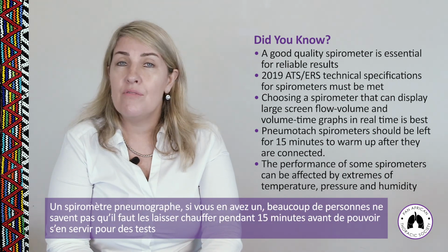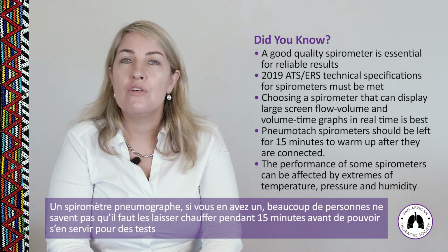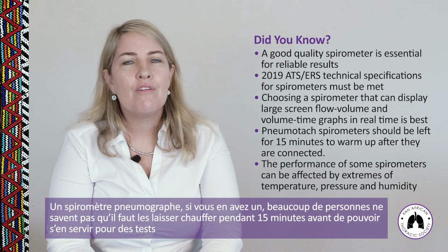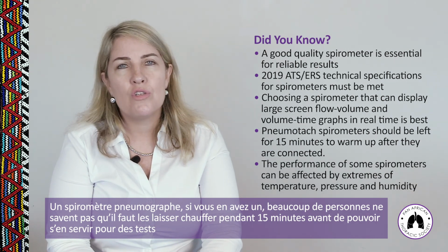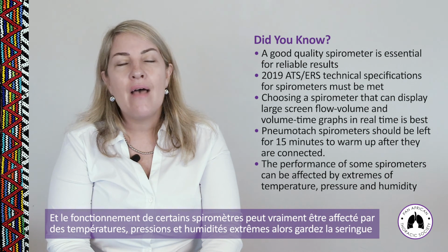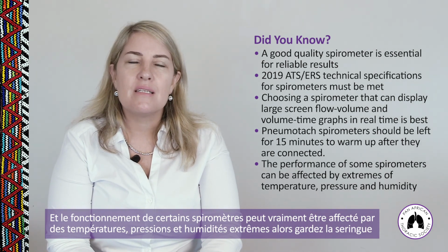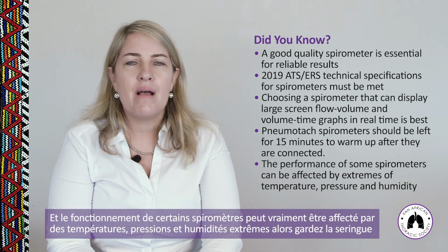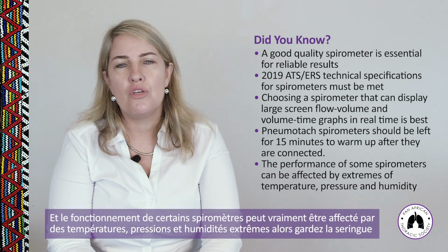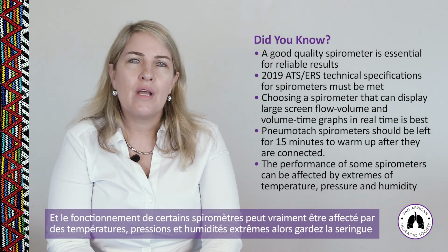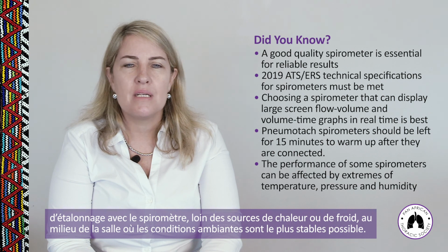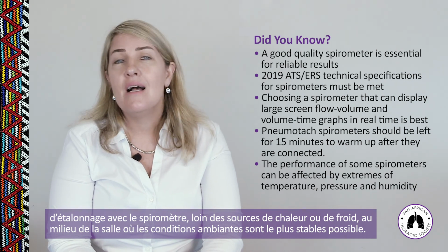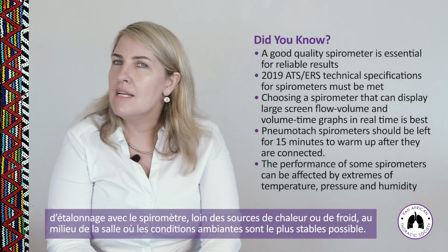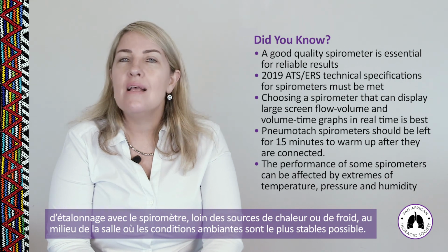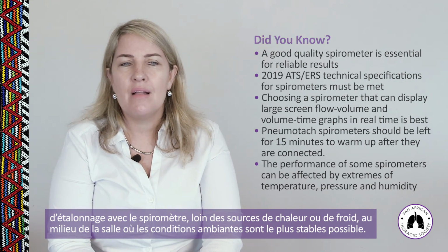Pneumotach spirometers, if you have one, some people don't know that you need to leave them to heat up for 15 minutes before you start to test using them. And the performance of some spirometers can be really affected by extremes of temperature, pressure, and humidity. So always store your calibration syringe with your spirometer away from heat, away from cold, just in the center of the room where ambient conditions are as stable as possible.